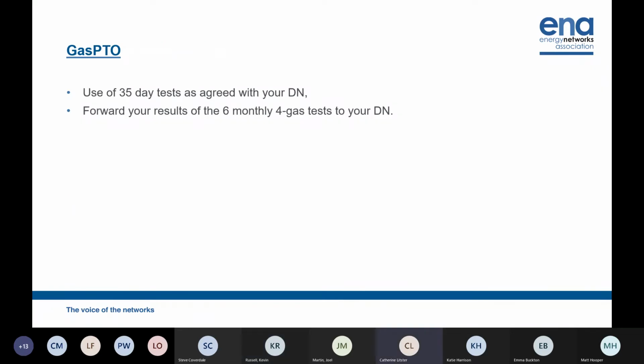Okay, just a couple on the gas PTO. Obviously, the gas PTO doesn't run a calibration gas, so we're using the 35-day test gas, and it'll be run as agreed with your DN, whatever schedule that would be, whether that be daily, weekly, or monthly. And the other stipulation from Ofgem at the moment is that every 6 months you will need to do a 4-gas test, which is the equivalent of the ISO 10723, and these need to be put in a report and sent to your DN to be forwarded on to Ofgem at the 6-monthly intervals.